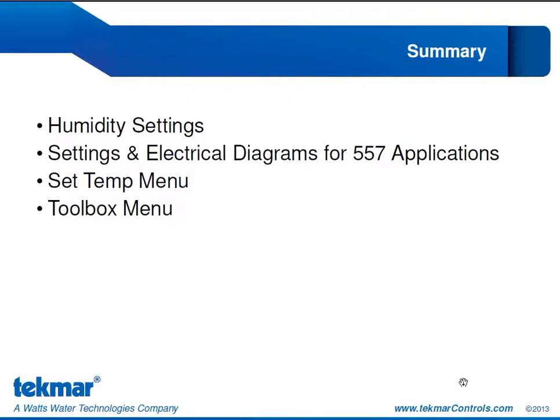To summarize today's presentation, we started by looking at relative humidity. What is it? How do we control it? We looked at the humidification modes and the dehumidification modes and how each mode is particular to a certain type of equipment so that we understand how we're going to configure the 557 for the equipment and the application that we're using. We looked at the essential settings and the electrical wiring for each of the 557 applications that are featured in the data brochure and that we went through in our first webinar. We talked about all the different menus of the 557, and we had a focus on the set temp menu and the toolbox menu and looked at the items that we can configure in the set temp menu and what kind of troubleshooting we can do in the toolbox menu.